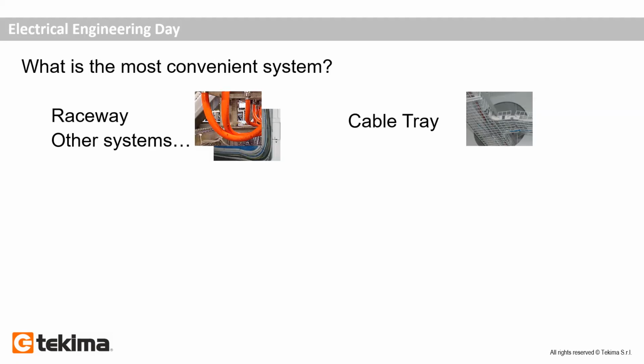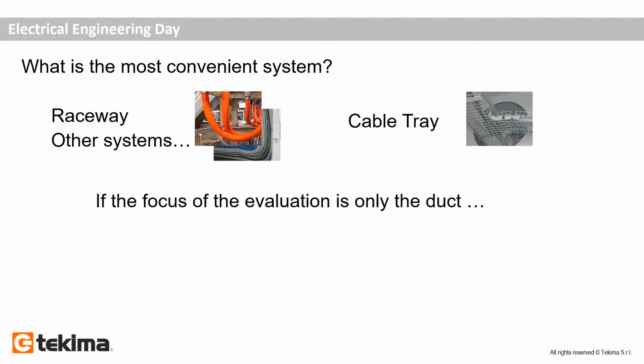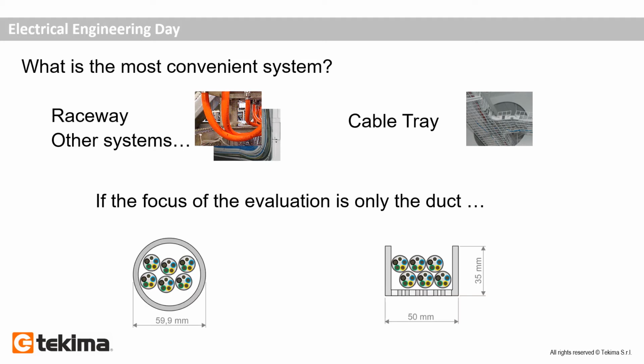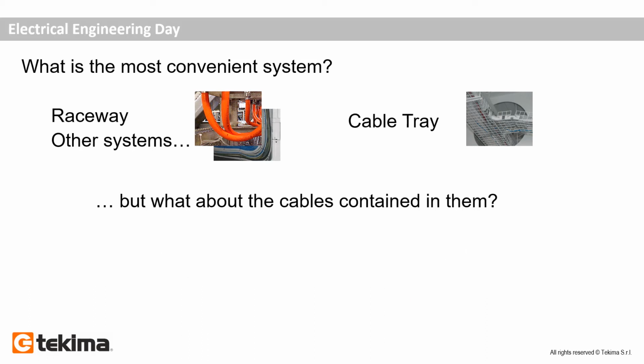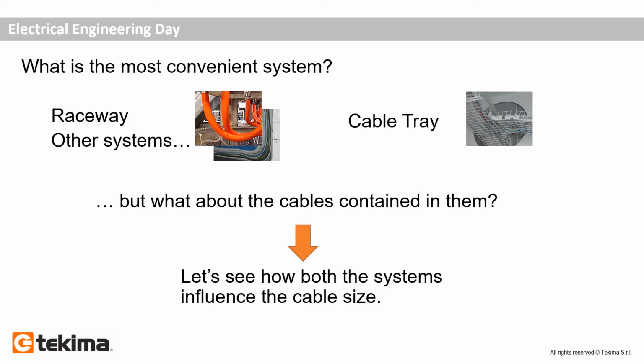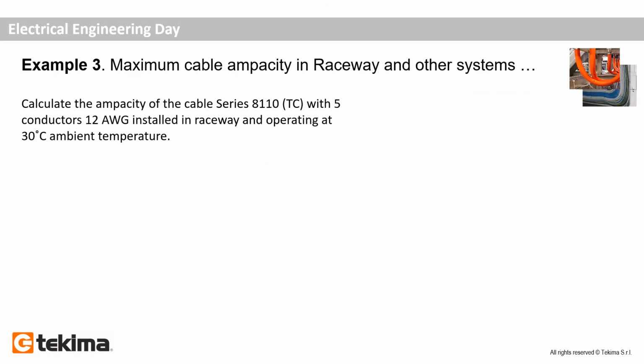What is the most convenient system between the raceway and the cable tray? Based on what we have seen till now, the selection of the two solutions can be based on the geometry, of course, and on the installation method that we have to apply. But are the two solutions influencing the cable's performance? Let's see with 2 other examples. Example 3. Calculate the ampacity of the cable series 8110 tri-cable exposed run with 5 conductors 12 AWG sized installed in a raceway and working at 30 degrees Celsius ambient temperature.